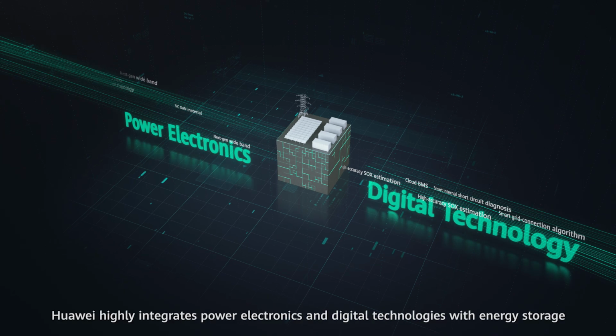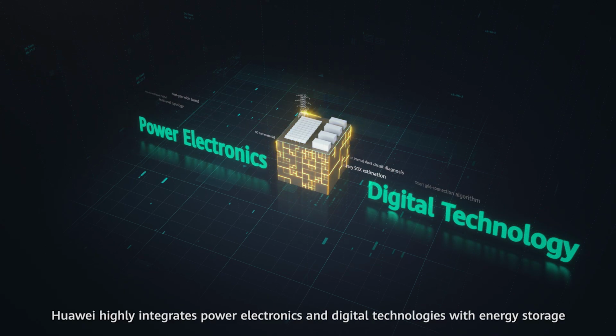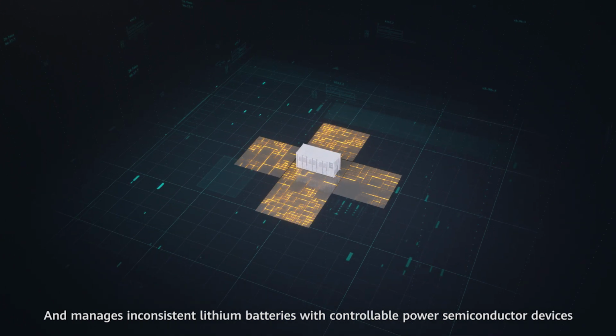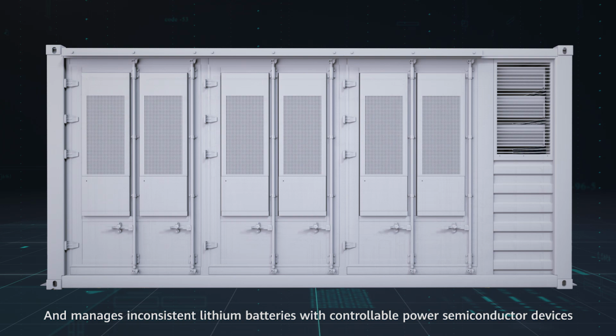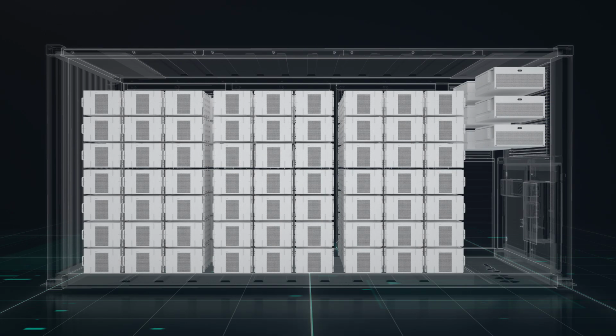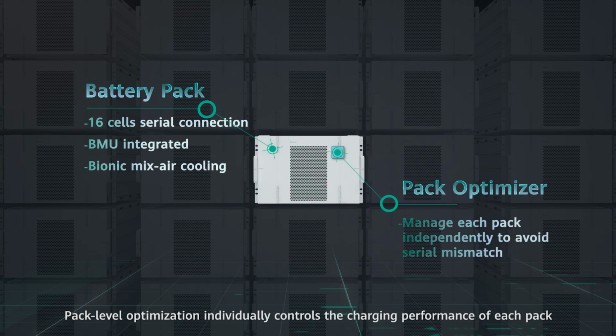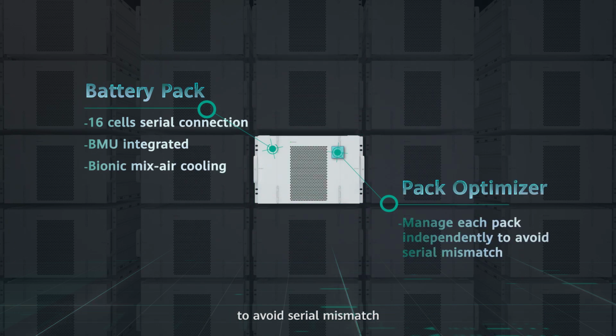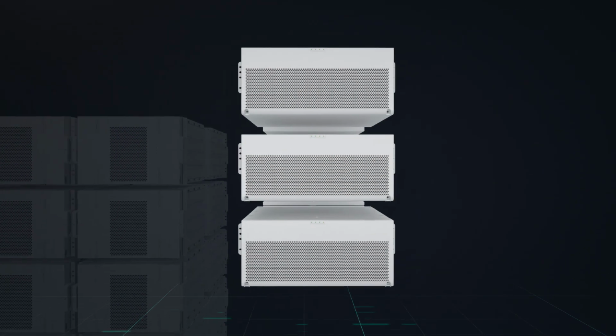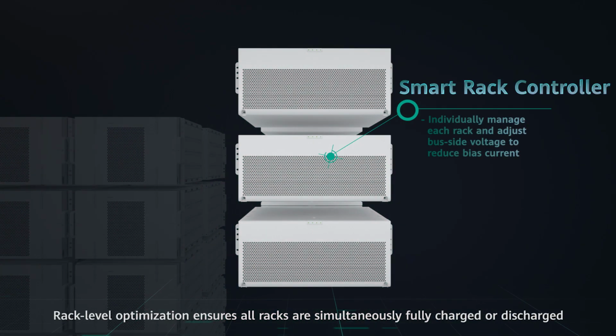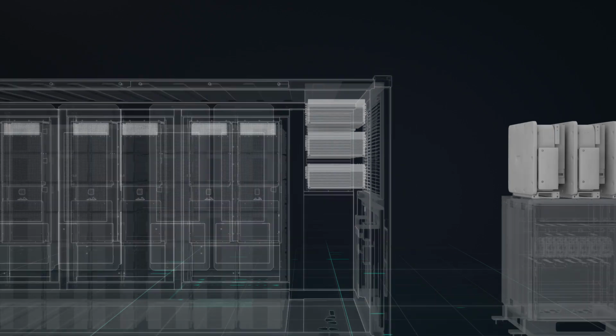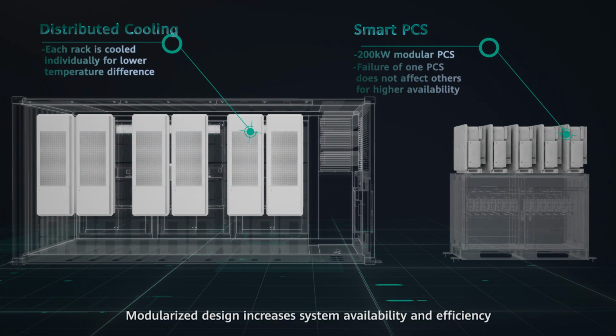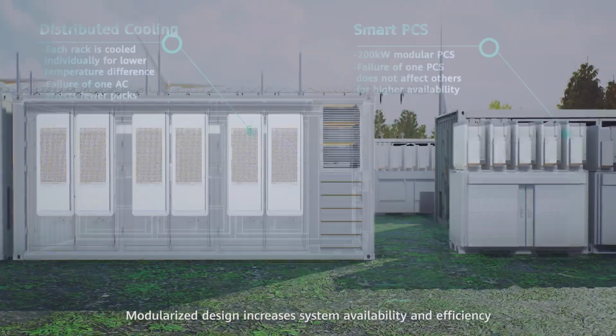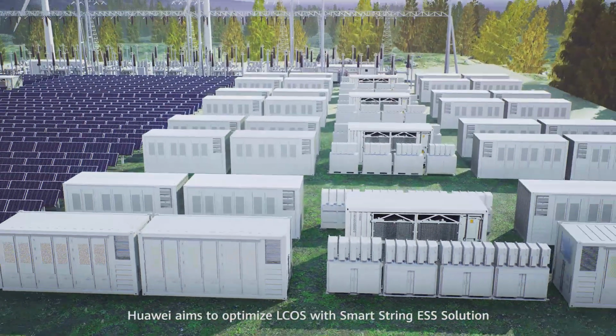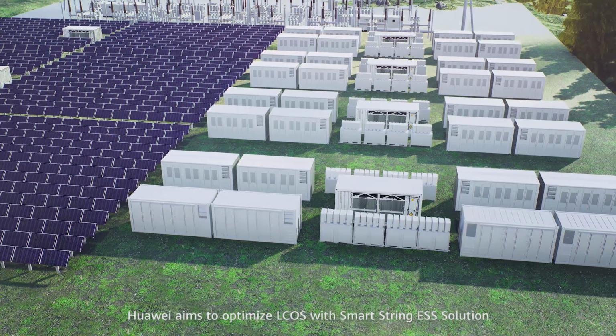Huawei highly integrates power electronics and digital technologies with energy storage and manages inconsistent lithium batteries with controllable power semiconductor devices. Pack-level optimization individually controls the charging performance of each pack to avoid serial mismatch. Rack-level optimization ensures all racks are simultaneously fully charged or discharged to avoid parallel mismatch. Modularized design increases system availability and efficiency. To sum up, Huawei aims to optimize LCOS with SmartString ESS solution.